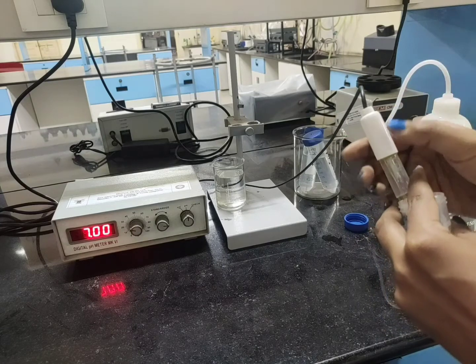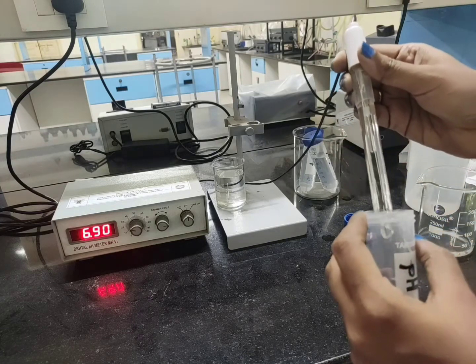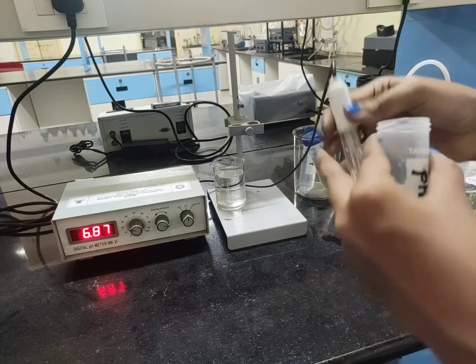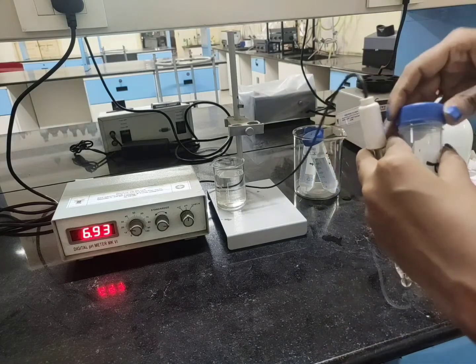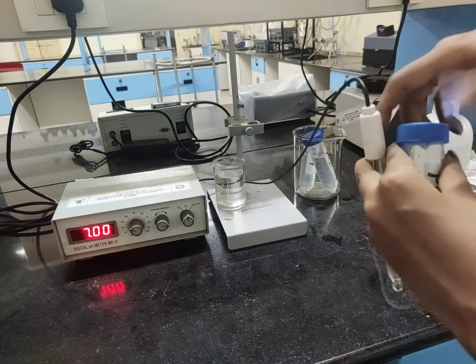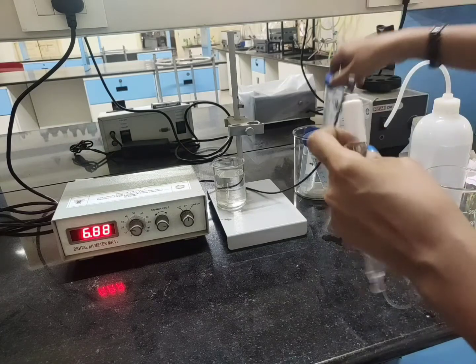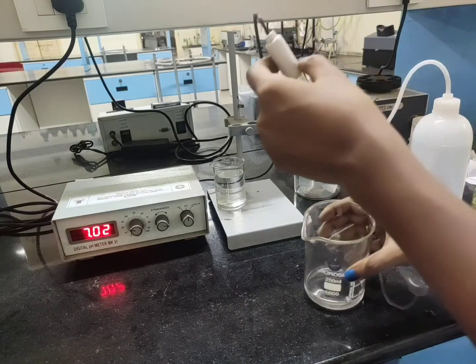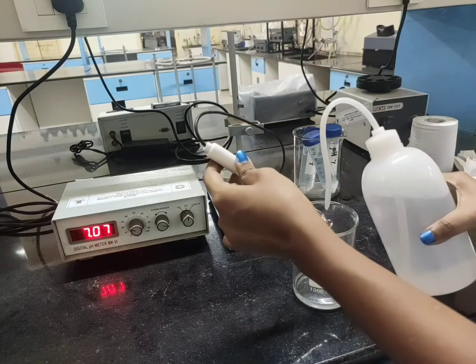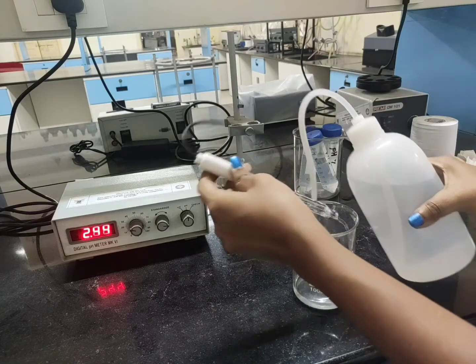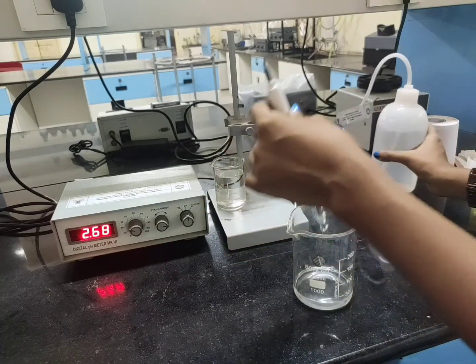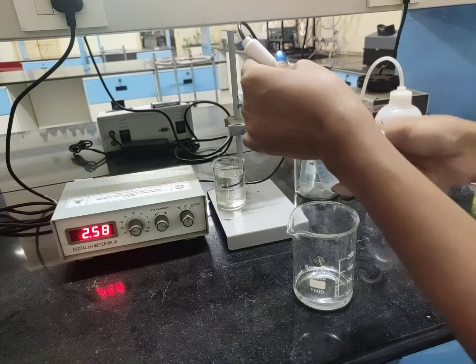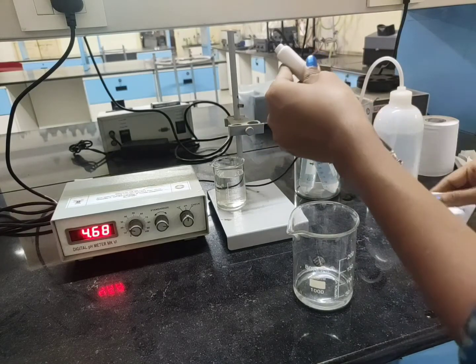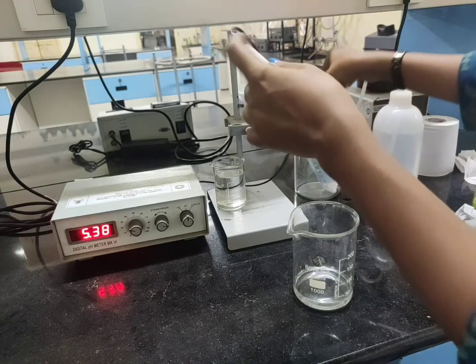Okay, so now that we got 7 and our pH buffer was also 7, we know that for 7 or for neutral pH the instrument is calibrated. So then what we are supposed to do is clean the probe again. You have to clean the probe and wipe it properly. So clean the probe or the glass bulb very properly, then wipe it gently, then take the next pH buffer, that is for pH 4.